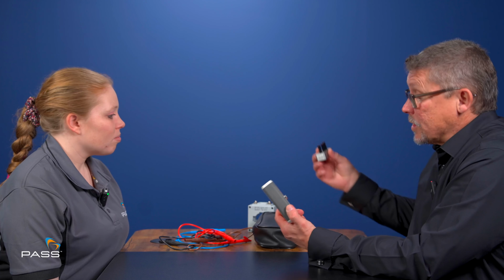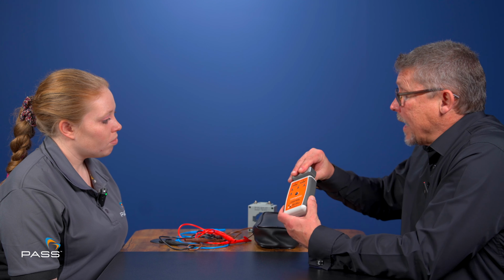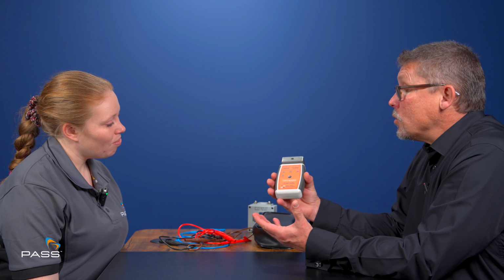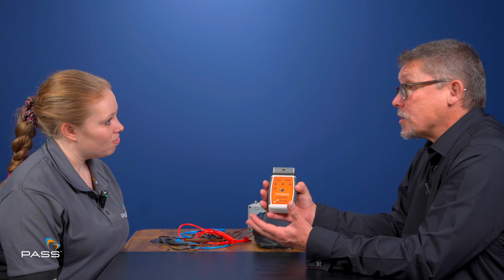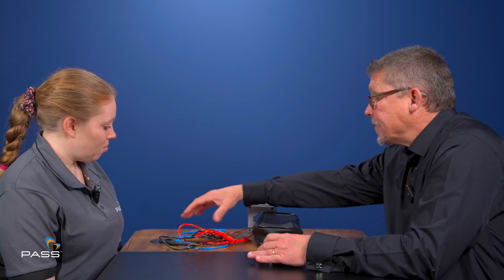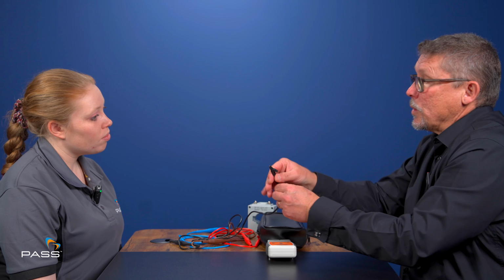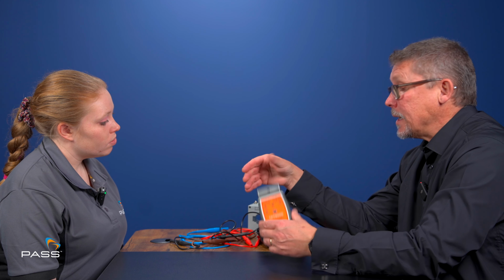The other thing is that we have a proving unit built in, so it's a self-contained unit that, once purchased, won't really need maintenance or calibration as such. Some companies may want to certify it, but the bottom line is we have everything in the unit you need to use it effectively. It comes with lead sets with small crocodile clips, but these are standard 4mm terminations, so you can put any accessory you might need into these lead sets. So the unit is a very simple, well thought out device.